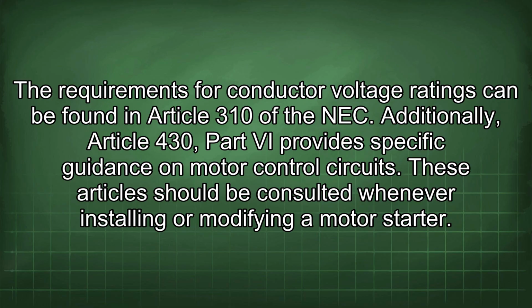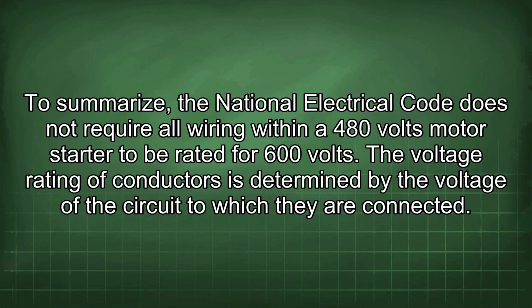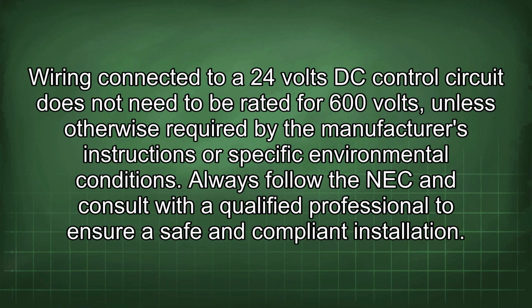Additionally, Article 430, Part VI provides specific guidance on motor control circuits. These articles should be consulted whenever installing or modifying a motor starter. To summarize, the National Electrical Code does not require all wiring within a 480 volts motor starter to be rated for 600 volts. The voltage rating of conductors is determined by the voltage of the circuit to which they are connected. Wiring connected to a 24 volts DC control circuit does not need to be rated for 600 volts unless otherwise required by the manufacturer's instructions or specific environmental conditions. Always follow the NEC and consult with a qualified professional to ensure a safe and compliant installation.